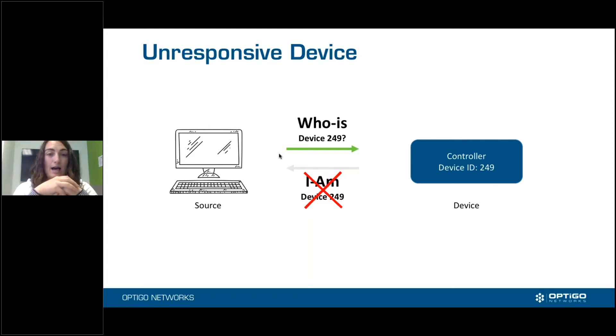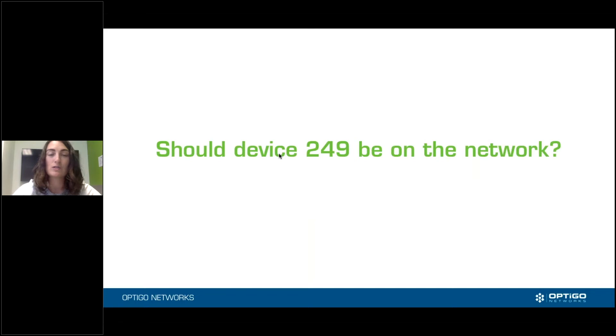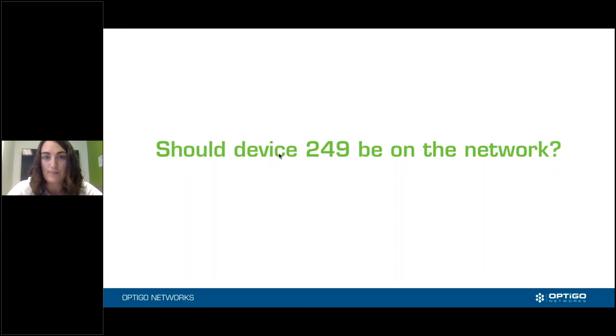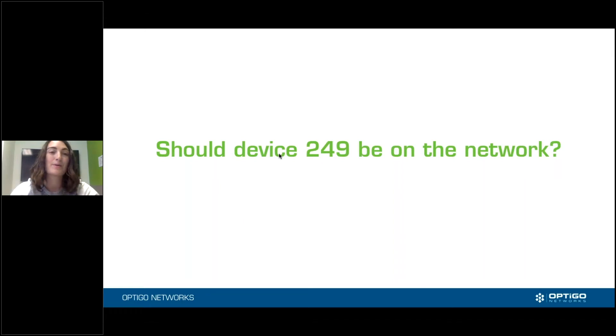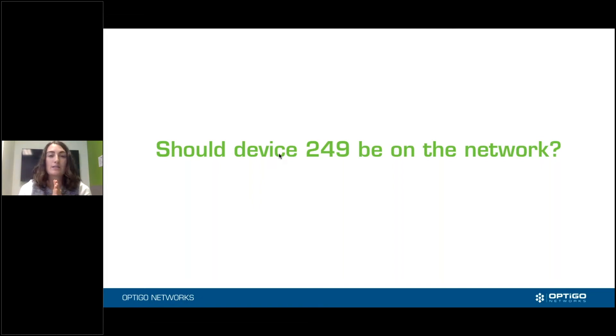There are a few different things this could mean, and we're going to work through what those are. The first question you want to ask yourself is: should device 249 be on the network? We often come across a situation where someone can just say no, 249 should not be on the network, because all of our device IDs or instance numbers — which are the same thing — are six digits. We start with the vendor code, then the building, and so on.